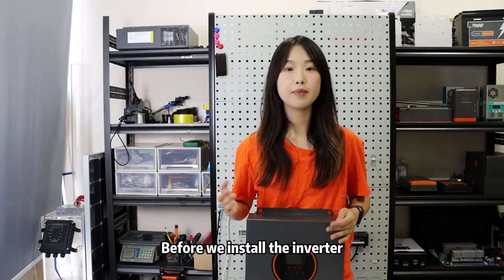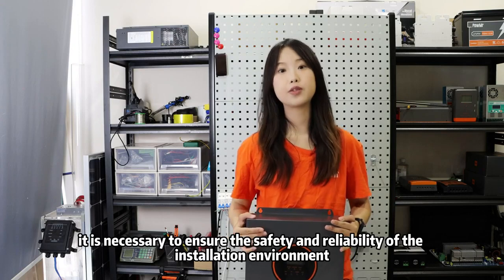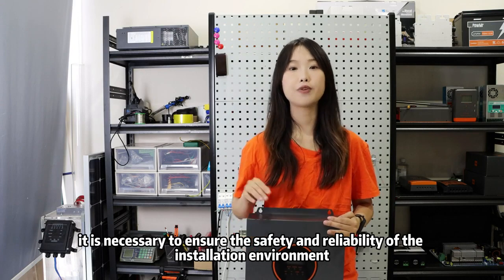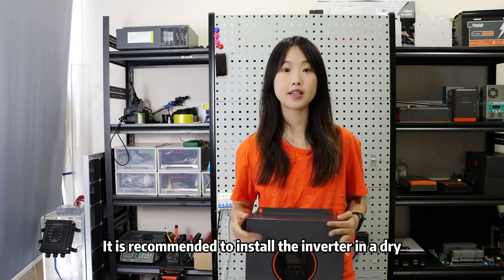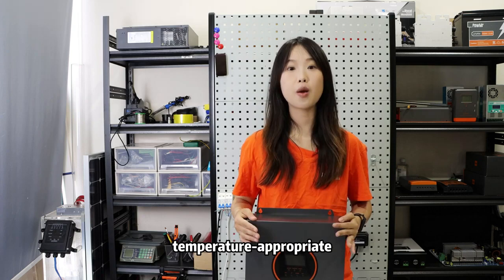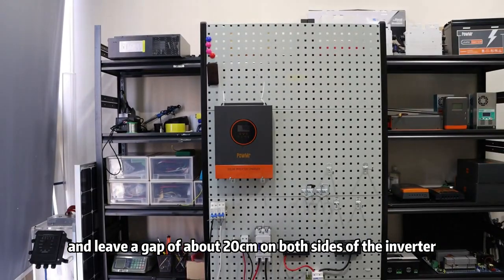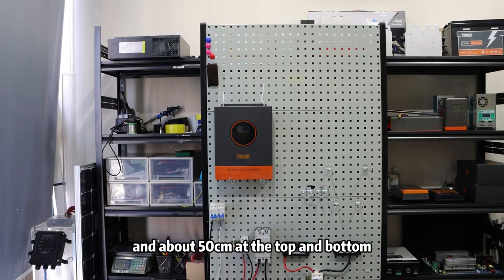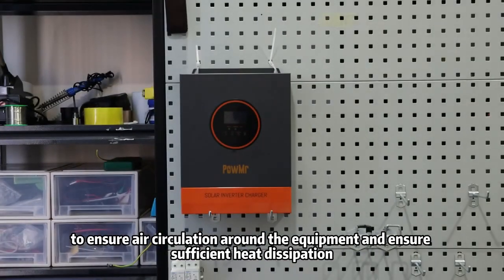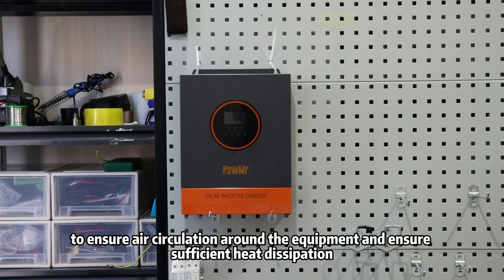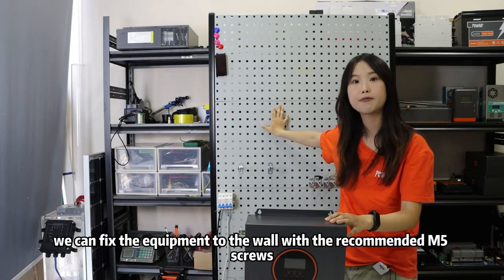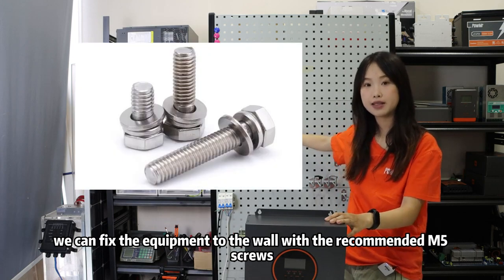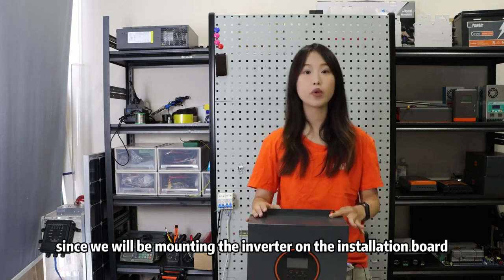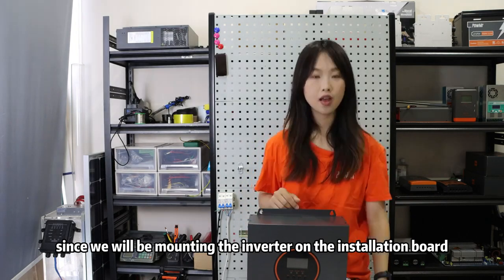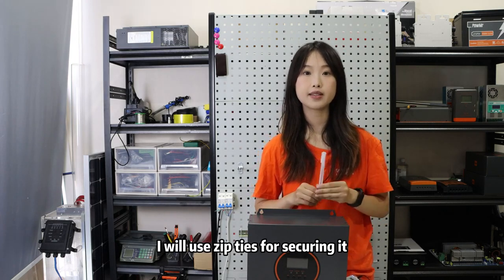Before we install the inverter, it is necessary to ensure the safety and the reliability of the installation environment. It is recommended to install the inverter in a dry, temperature appropriate, and well-ventilated room, and leave a gap of about 20 cm on both sides of the inverter and about 50 cm at the top and bottom to ensure air circulation around the equipment and sufficient heat dissipation. After confirming the location, we can fix the equipment to the wall with the recommended M5 screws. However, since we are mounting the inverter on the installation board, I will use zip ties to secure it.